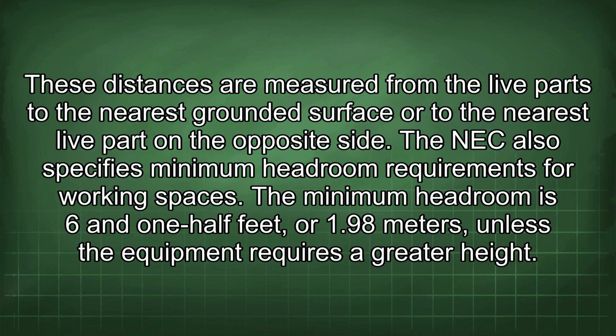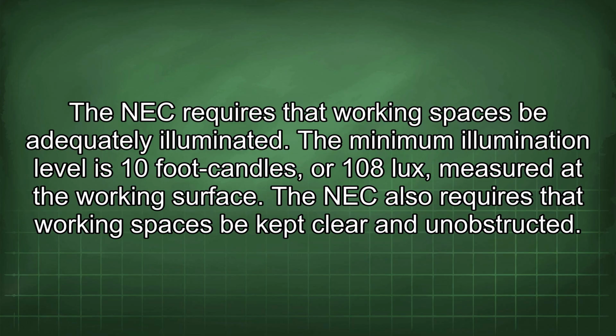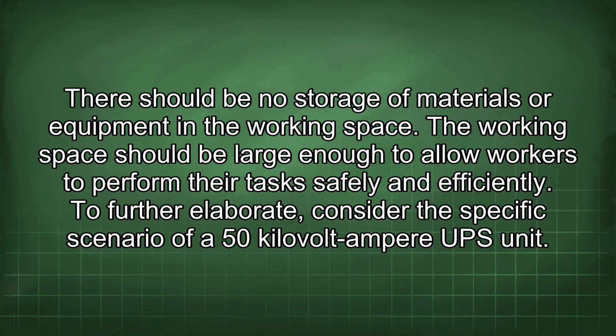The minimum headroom is 6½ feet, or 1.98 meters, unless the equipment requires a greater height. The NEC requires that working spaces be adequately illuminated. The minimum illumination level is 10-foot candles, or 108 lux, measured at the working surface. The NEC also requires that working spaces be kept clear and unobstructed. There should be no storage of materials or equipment in the working space. The working space should be large enough to allow workers to perform their tasks safely and efficiently.